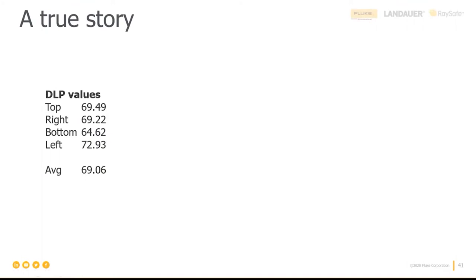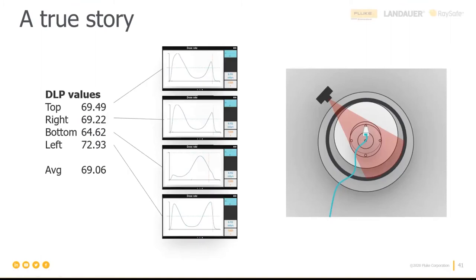So the first time they tried the X2 CT sensor for this, they could immediately tell from the waveform what was happening. And with the help of this, they can now save unnecessary measurements and disregard only the ones giving the wrong dose. So let's have a look at these numbers. We have the four measurements from top, right, bottom, and left. Here are the corresponding waveforms.